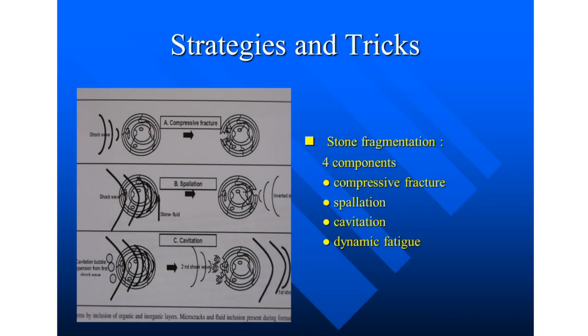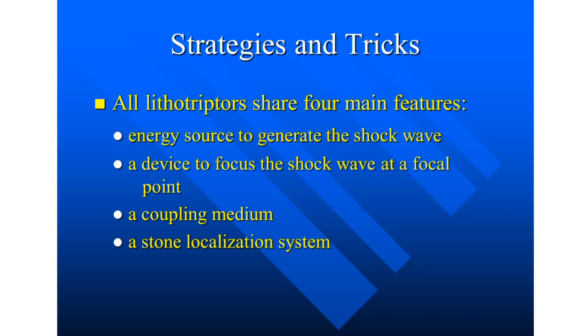So when we look at lithotripters, the energy source to generate the shock wave is the consideration. It's either going to be the original spark gap or now the newer electromagnetic units. The device has to have a way to focus the shock waves at the second focal point. There has to be a coupling medium, and there has to be a stone localization system. Either that's going to be fluoroscopy, or in some of the newer units now, we're going to use ultrasound.